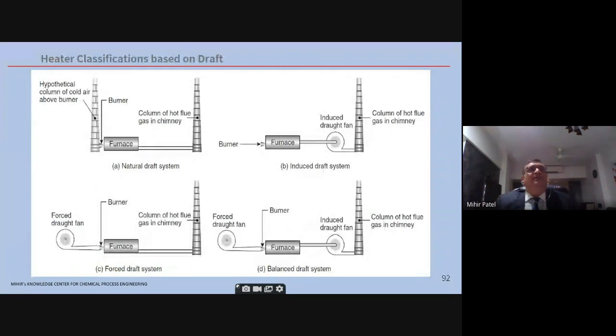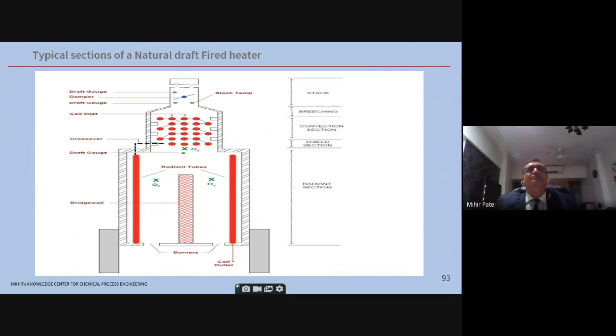Based on draft, you have four types of draft. Natural draft system on the left. Because of the hot flue gas buoyancy, it is creating a draft inside the fire heater. This is basically low efficiency, and you don't use this for very large heaters. You have the ID fan, the induced draft system, where the ID fan is there. Then you have the forced draft system and the balanced draft system. For very large heaters, balanced draft gives the maximum efficiency.